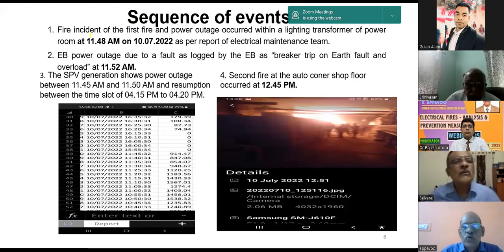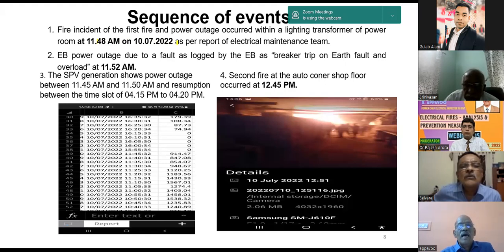There were two fires that occurred in that premises. The first one was inside a lighting transformer. There is a lighting transformer inside the electrical panel, main HT to LT panel, where normal people do not approach. A fire got ignited inside the dry-type lighting transformer itself. It was extinguished by the people after switching off the light. But when that fire occurred was ascertained as 11:48 a.m. on 10/07/2022, simultaneously with a power failure.